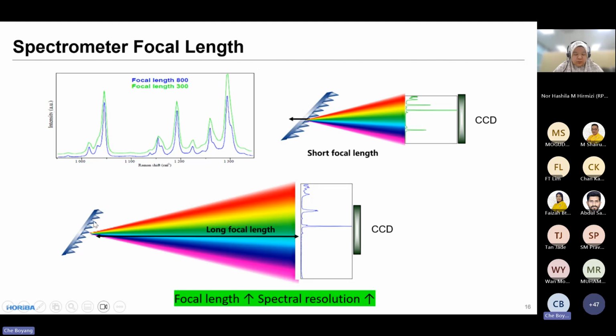The grating is the part that will disperse your signal based on the wavelengths like this. So if you have a longer focal length, your signal will traverse a longer distance, and it will be dispersed wider. You can see this comparison between the short focal length and the long focal length. The long focal length will disperse your signal wider.